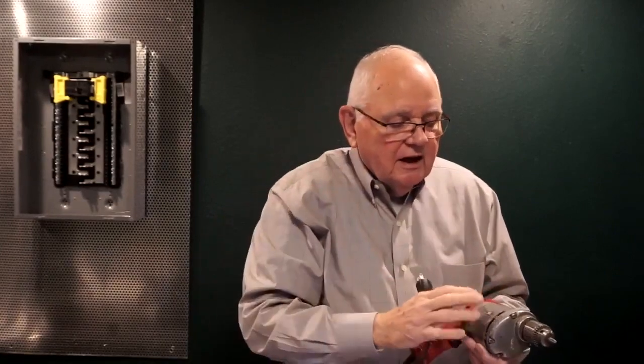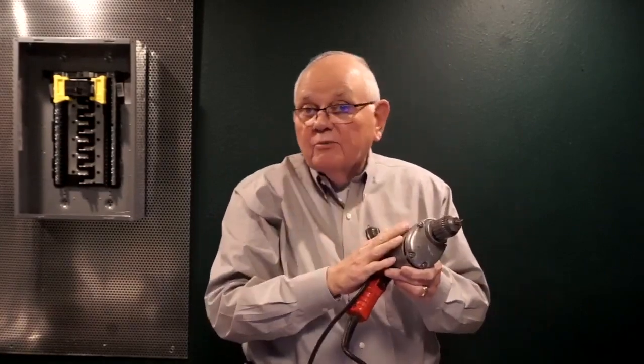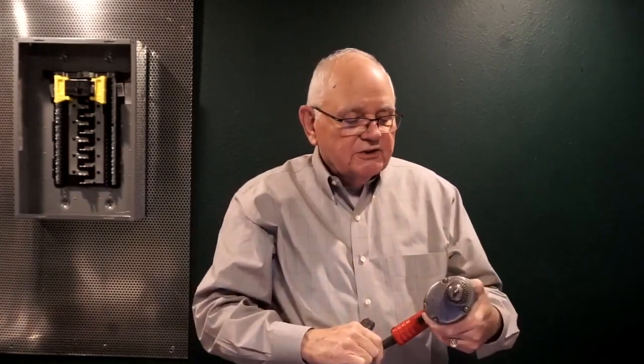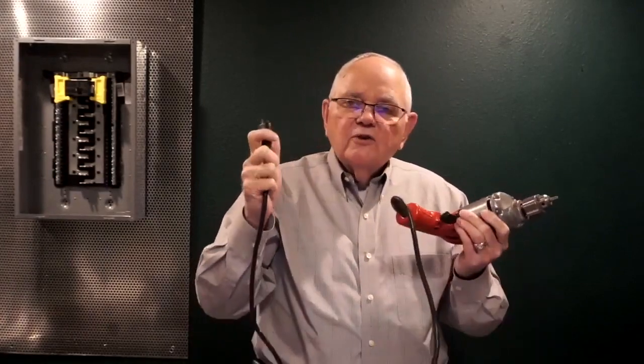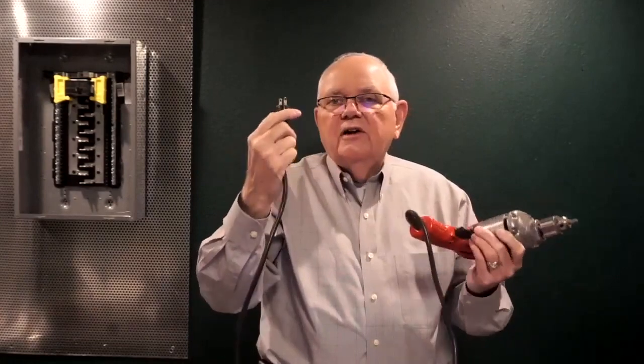But anyway, now we use a lot of battery operated portable power tools and so forth. But we were required to go through every 90 days and check this on our extension cords and portable tools. And we have to have a written program in place and somebody designated to be in charge of that program. So for all of the rules, take a look in NEC Article 590. Okay? NFPA 70E, of course, provides us a lot of information on shock protection.